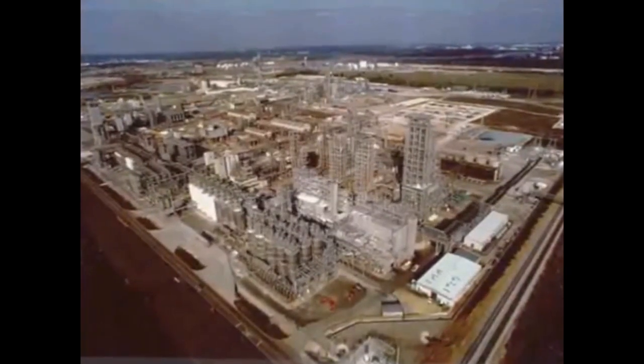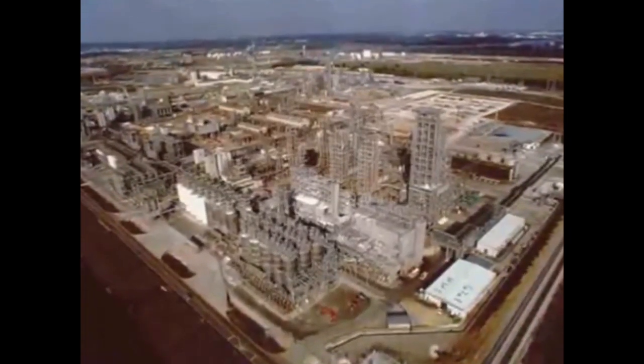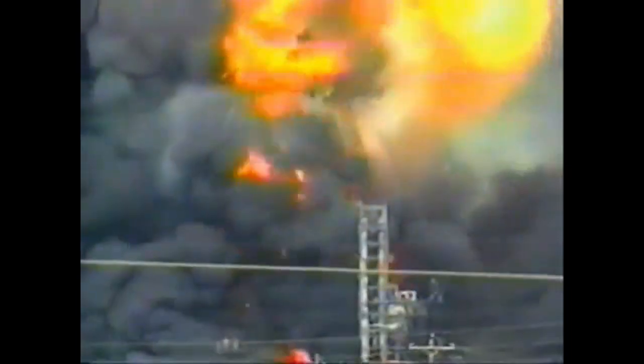According to a report from FEMA, the Phillips company needed to be more available to inspection by engineers and safety officers, in addition to inspection by local fire departments who may not be as knowledgeable about the potential hazards. Furthermore, it was noted that safety valves and connections should be underground as much as possible to minimize damages from the explosion. In this explosion, the sprinkler system was above ground and was cut off by the blast, preventing any immediate control of the following fires.